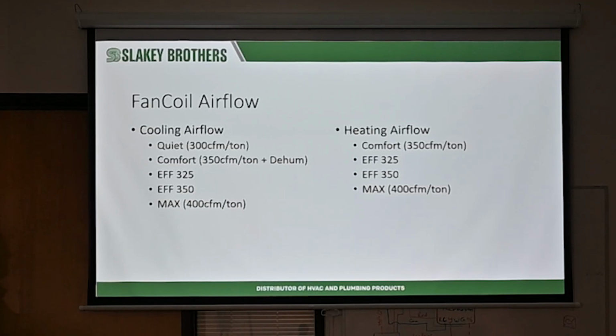Again, a 5-ton furnace for a 3-ton unit. You don't have to do the 400 CFM per ton. You can just do dip switches to get that 1200 CFM. So in this case, if we adjust airflow to quiet mode, it decreases airflow to 300 per ton. Gotcha. So if you've got a scenario where they're like, hey, let's do the quiet one, too much air, for example.